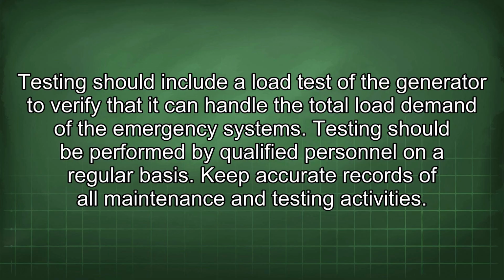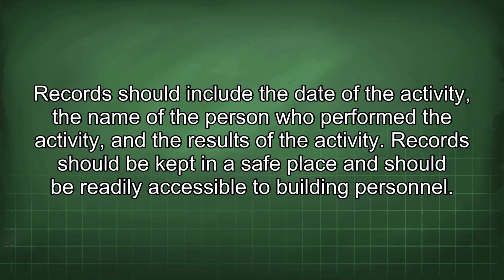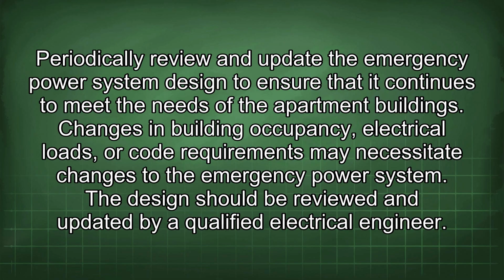Keep accurate records of all maintenance and testing activities. Records should include the date of the activity, the name of the person who performed the activity, and the results of the activity. Records should be kept in a safe place and should be readily accessible to building personnel. Periodically review and update the emergency power system design to ensure that it continues to meet the needs of the apartment buildings. Changes in building occupancy, electrical loads, or code requirements may necessitate changes to the emergency power system. The design should be reviewed and updated by a qualified electrical engineer.